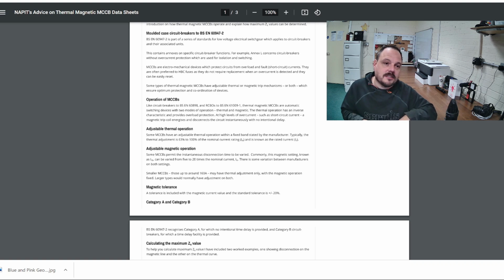When you're talking about distribution circuits to other distribution boards on large installations, you really don't want to be stacking up typical circuit breakers, so your MCBs, in series, because getting selectivity between them is really, really difficult. Even when you're using MCCBs, you will often only achieve partial selectivity, but it's a lot better. And you can use fuses as well, which usually give you better selectivity, but the issue is if you have a fuse go out, it involves an electrician having to come and replace that fuse and restore power to the circuit, whereas with an MCB or an MCCB, within reason, that can be user controlled as long as they have some knowledge of the electrical system.